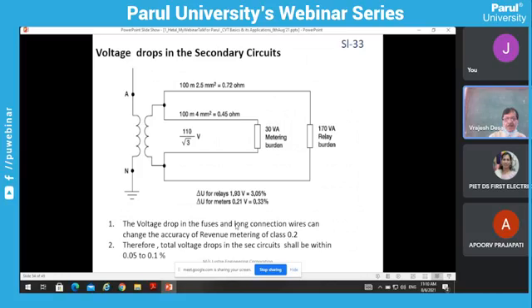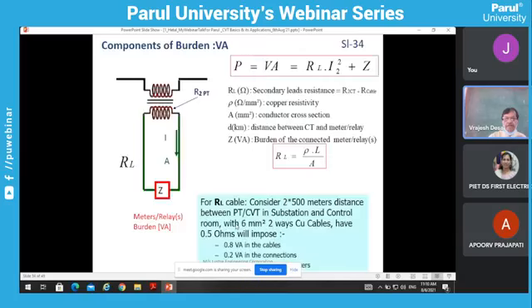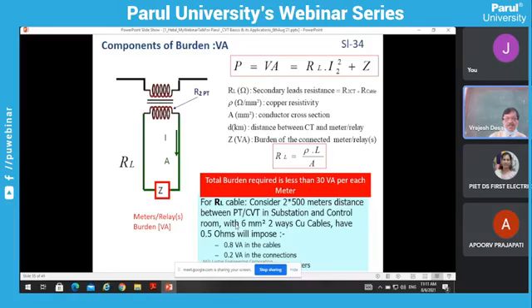So here we have to see the voltage drop in the connecting wires because that will hamper the accuracy. Normally the voltage drop in the secondary circuit shall not be more than 0.1%. So you have to select the gauge wire of the cable connections of a particular size. It is shown over here that it should be minimum 6 mm square cable and it should be copper, so that conductivity being very high, the drop will be very low. So it will provide the voltage drop. I mean the VA taken away by the cables is 0.8 VA, and 0.2 VA is for the connections and of the relays and meters. This is very low because nowadays we have digital and numerical relays available. So total burden required is sufficient at 30 VA.